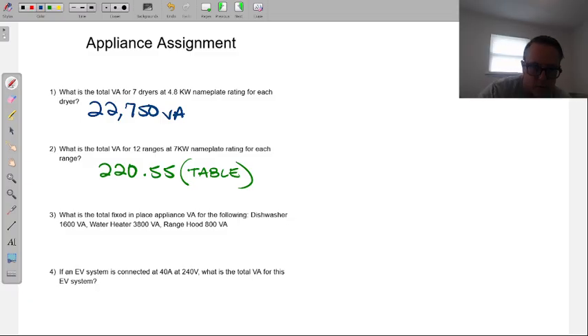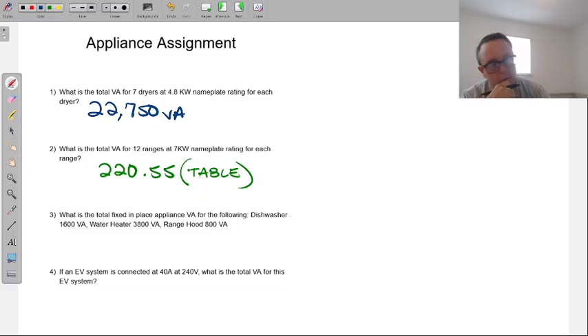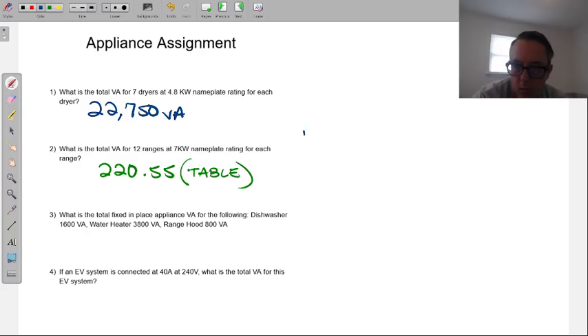Now with this one, there's no minimum. Again, the approach is houses come with the oven or the range setup, so we just treat it, no issues with the kilowatts, whatever it's telling us. Then we're going to multiply by the correction factor for 12.